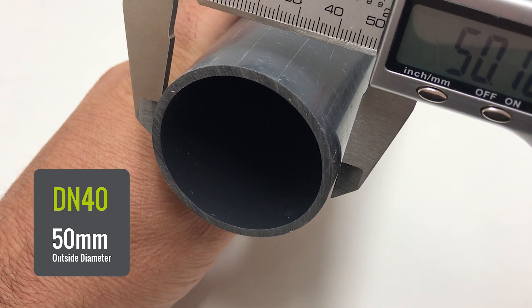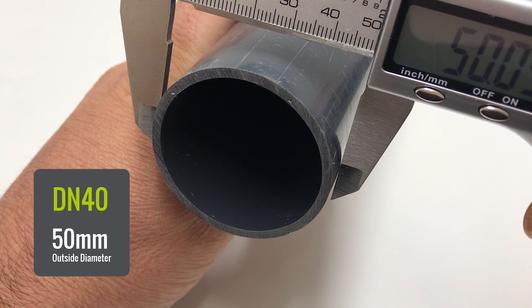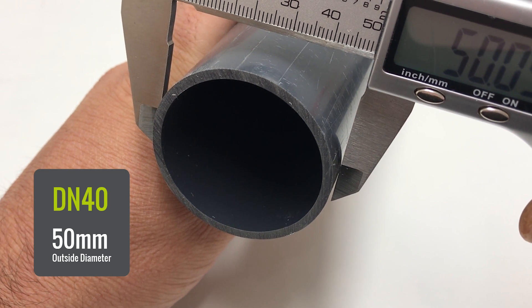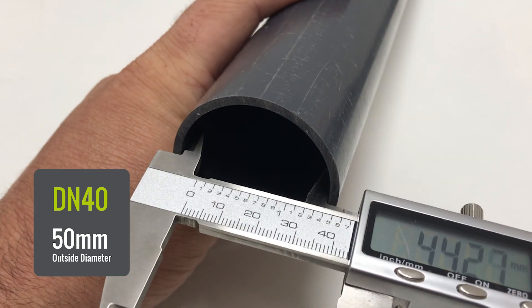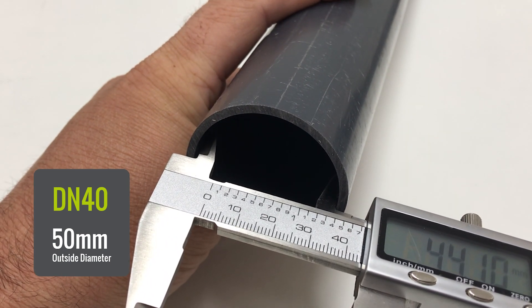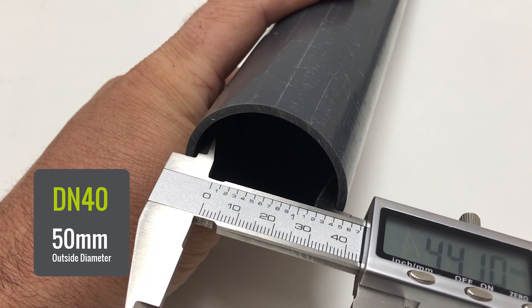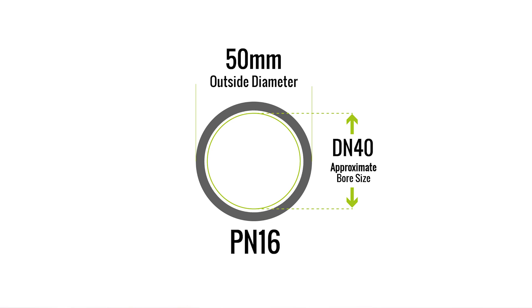Here I have a small sample of uPVC pipe with an outer diameter of 50 millimeters. Now let's look at the actual inner diameter — we are measuring just over 44 millimeters for the inner diameter. You'll see that the actual inner diameter differs between pipes of the same size designation depending on the pipe's pressure rating, but both pipes are classed as DN 40.